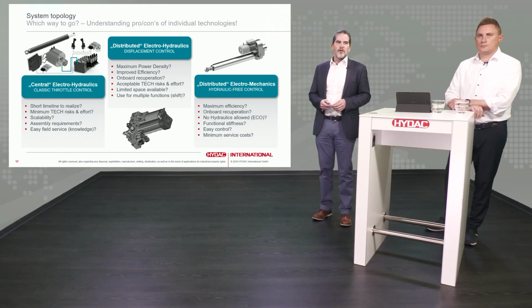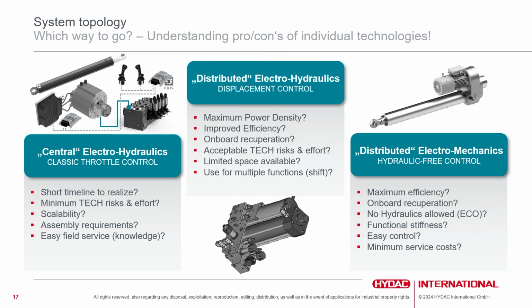If you look at the different solutions, going in the direction of a central hydraulic, you typically have a motor system with an inverter, a control unit. Attached to the motor is a pump - it could be a complete power pack like you see here. Then you have your throttle valve to operate the individual functions. I only showed one cylinder function here because of space, but it could be up to 10 functions supplied by this one individual pump.